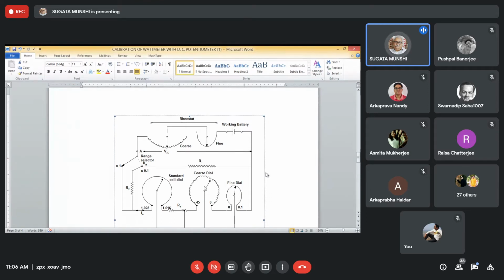It is a resistive potential divider with the help of which you scale down the voltage that you want to measure. Suppose you want to measure a voltage of 200 volts. So you scale it down to the range of voltage that this DC potentiometer can allow with the help of this voltage ratio box. Then you measure it with the help of DC potentiometer, multiply it with the voltage ratio box multiplying factor to get the actual voltage.